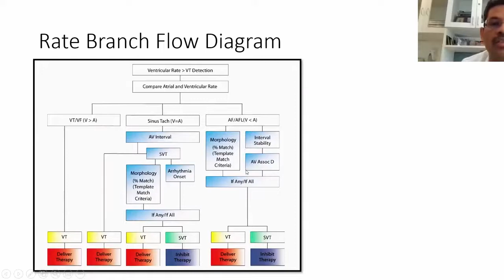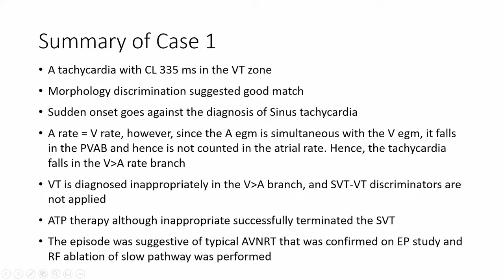So just to summarize this case, this was a tachycardia with a cycle length of 335 milliseconds in the ventricular tachycardia zone. The morphology discrimination suggested good match, and the sudden onset goes against the diagnosis of sinus tachycardia. But SVT, VT discriminators were not applied since the device diagnosed it in the V more than A rate branch. Since the atrial EGM is simultaneous with the V EGM, it fell in the post-ventricular atrial blanking, hence it is not counted in the atrial rate. Hence the tachycardia falls in the V more than A rate branch, and VT was diagnosed inappropriately. And ATP therapy, although inappropriate, successfully terminated the tachycardia. And the pattern of the episodes, initiation by a PAC and a good morphology match, all suggested a diagnosis of typical AVNRT that was confirmed on the EP study, and RF ablation of slow pathway was performed in this case.